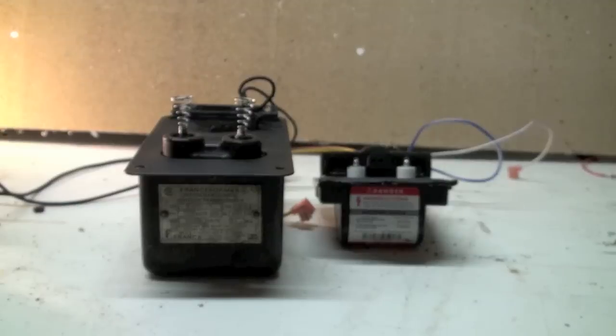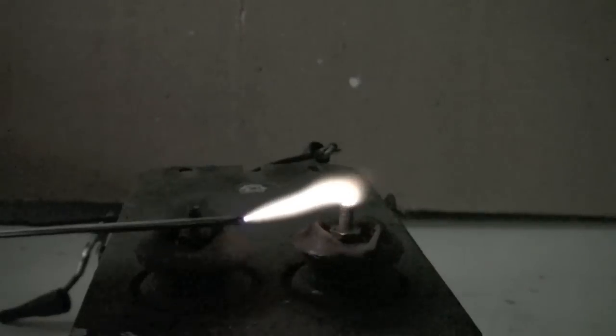Now we're going to compare a good transformer with a bad transformer. This one's a good one, so you can take and draw that spark way across there. Almost comes all the way over to the other electrode.